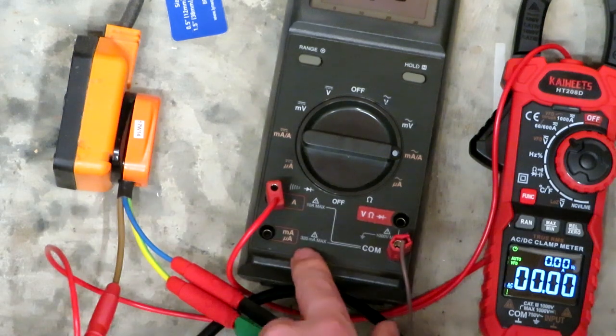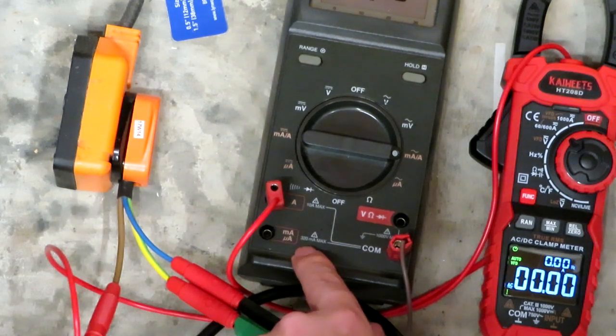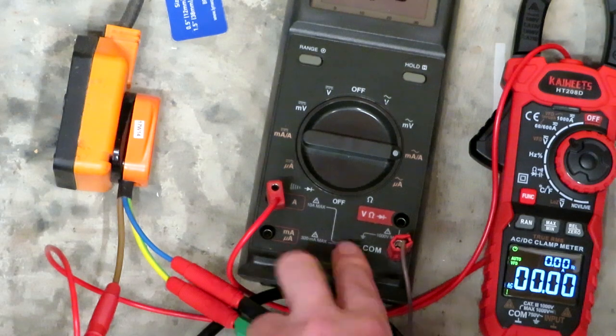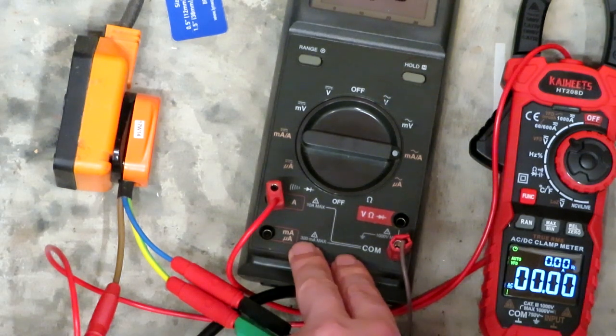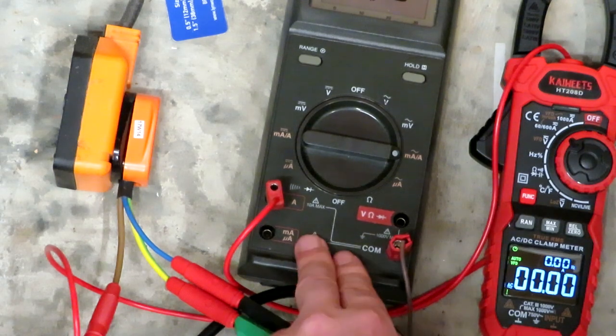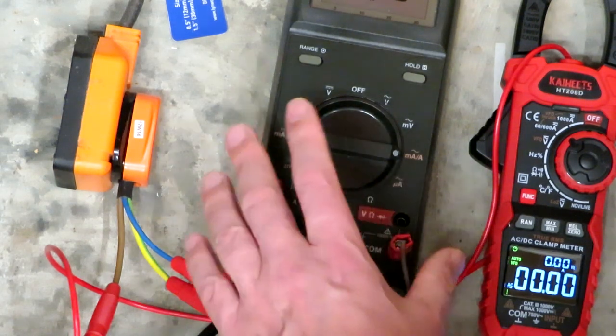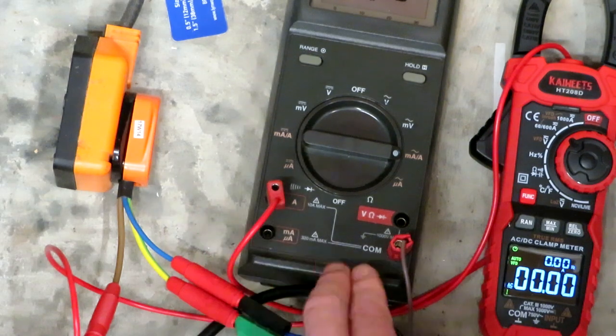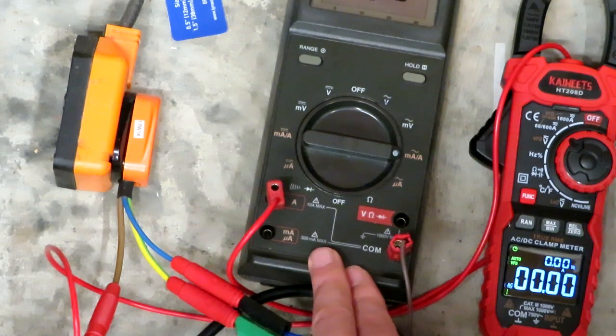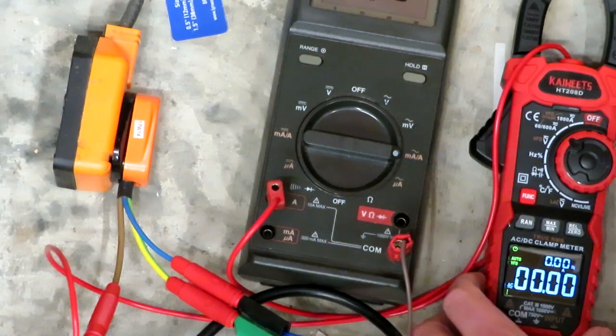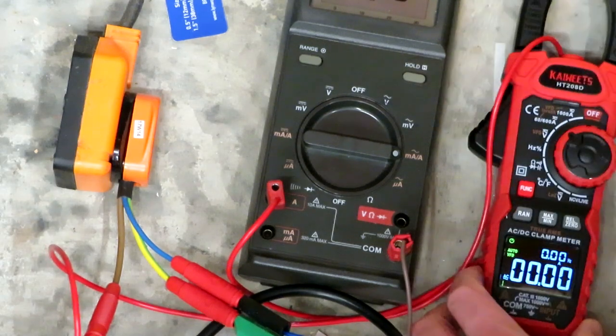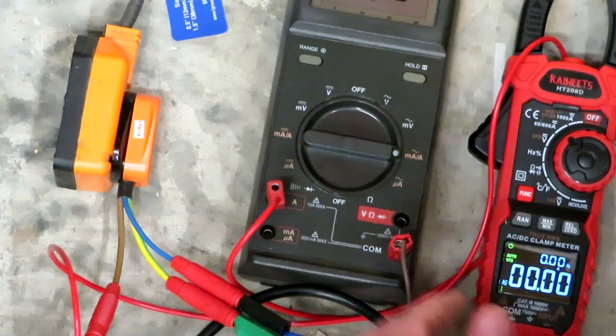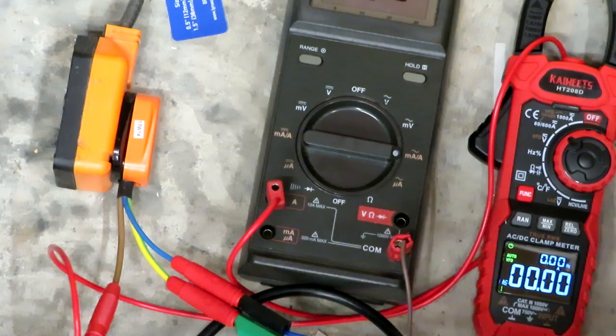So what happened was when we switched the machine on, it blew the 200 milliamp fuse in the meter, and that disconnected the electrical supply going to the milling machine and everything went off. Now, although for me this is quite annoying because I now have to replace a fuse in the meter, I think it also gives you a good example of why making non-contact measurements using a clamp meter is a safer way of doing it, because you're less likely to make this kind of silly connection error.